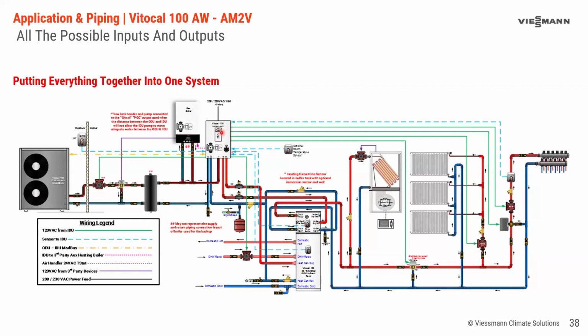And the indoor unit is going to have all the control logic in there. The really great thing about this is the indoor unit will give you all sorts of diagnostics on what the outdoor unit is doing. If you want to know the fan speed, the refrigerant pressures, the refrigerant temperatures, all of that can be measured from the indoor unit controller. So troubleshooting is very easy. Before you get out there and try to figure out what's wrong with the outdoor unit, you can look at the indoor unit and run a diagnostic to see where you need to start.